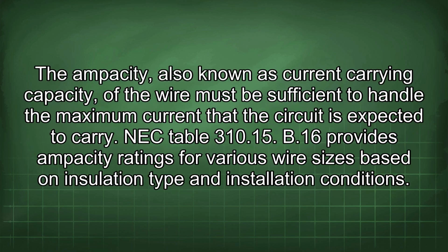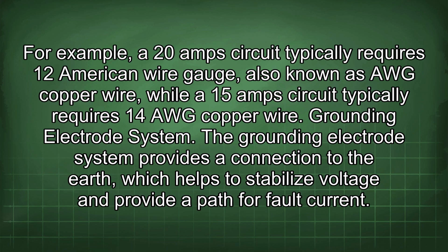The ampacity, also known as current carrying capacity, of the wire must be sufficient to handle the maximum current that the circuit is expected to carry. NEC Table 310.15(B)(16) provides ampacity ratings for various wire sizes based on insulation type and installation conditions. For example, a 20 amp circuit typically requires 12 American wire gauge, also known as AWG, copper wire, while a 15 amp circuit typically requires 14 AWG copper wire.